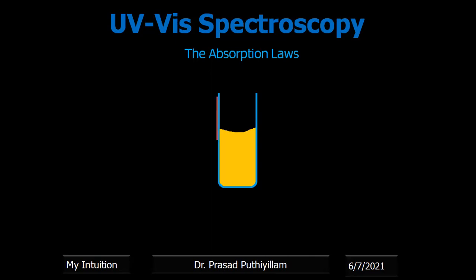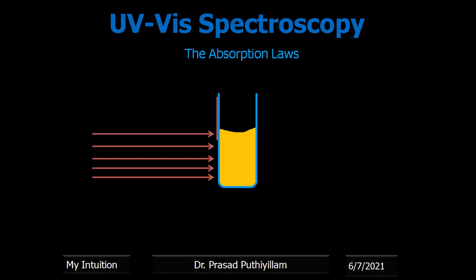Okay, so here is the cuvette, and I represented it here with a colored line. That means the cuvette is not clean, this portion is not clean. That means if a light comes and hits the surface, wherever the incident light hits a surface which is not clean, or if the surface is rough, the cuvette glass surface, if it is rough, if any scratches are there, or if it is not clean, or even if it contains solvent molecules or water molecules, then some of the light may get reflected.